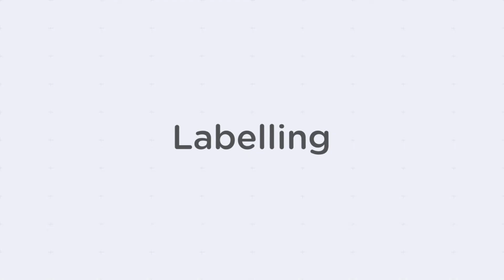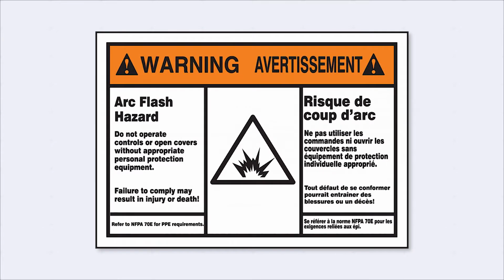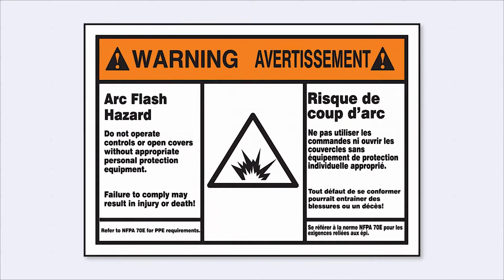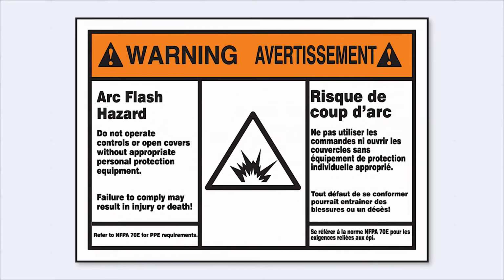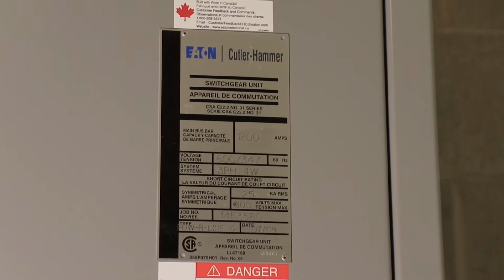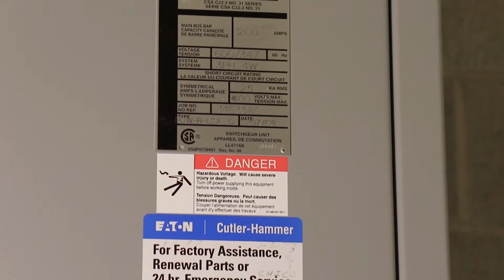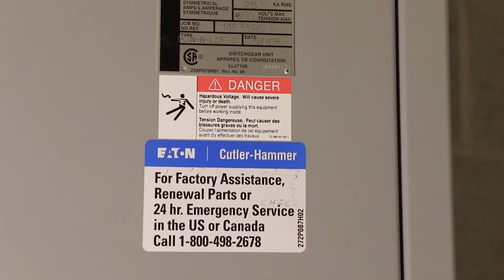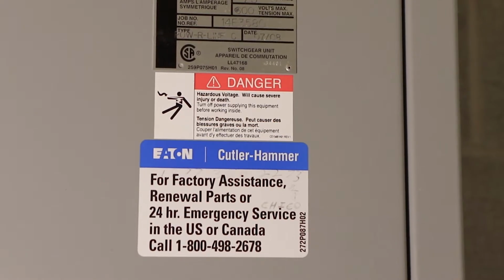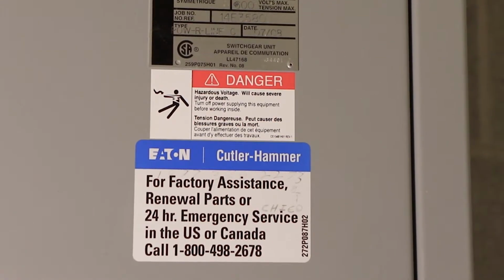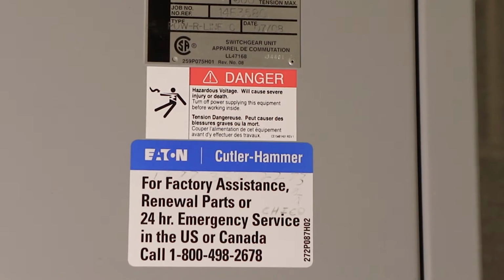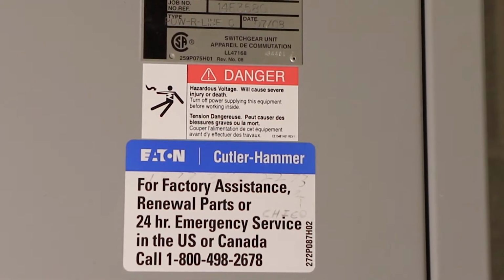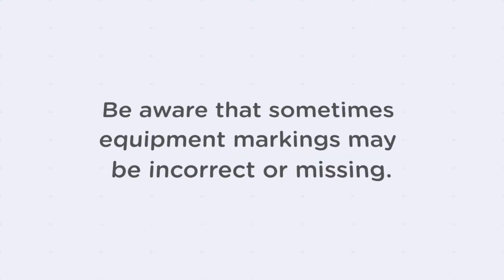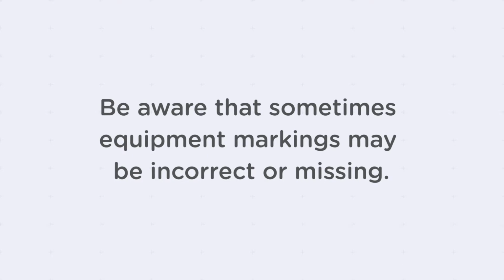The shock and arc flash analysis will provide the information required to develop an arc flash and shock hazard label. The Canadian Electrical Code requires that electrical equipment likely to require examination, adjustment, servicing, or maintenance while energized shall be field marked to warn persons of potential electric shock and arc flash hazards. Be aware that sometimes equipment markings may be incorrect or missing.